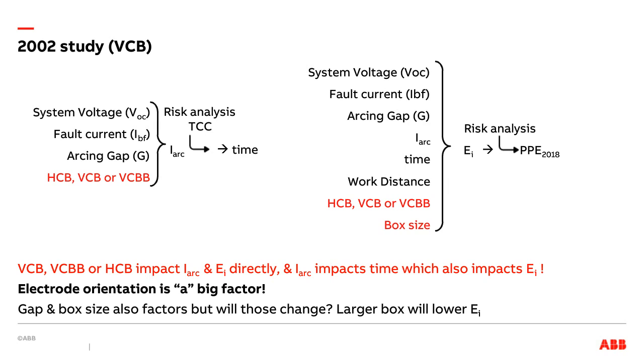The net issue here is that your big impacting variable is that electrode orientation, which impacts both arcing current, seen on the left here, and the incident energy seen on the right. That horizontal, vertical, or vertical with a barrier impacts both of those calculations. So we know that the electrode orientation is a very big and important factor.